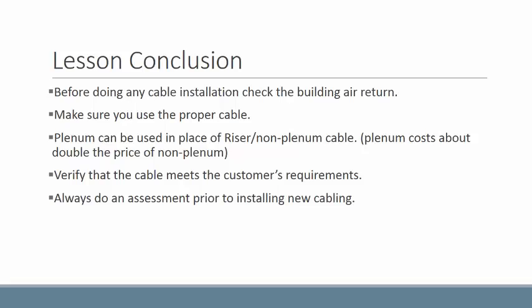In conclusion, before doing any cable installation, check the air return of every building. Make sure you use the proper cable. Remember, plenum cable can be used in place of riser non-plenum cable. However, plenum costs about double the price of non-plenum cable.